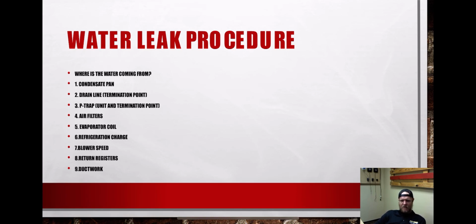The condensate pan, what does it look like? Is there buildup in it? Do you need to clean it? The drain line, where's the termination point? Don't just start blowing things out if you don't know where the termination point is. Bigger stores, usually there's a termination point inside of the slop sink or inside the janitor's closet into a slop sink. However, it's not always. So make sure that you find that termination point prior to blowing anything out.